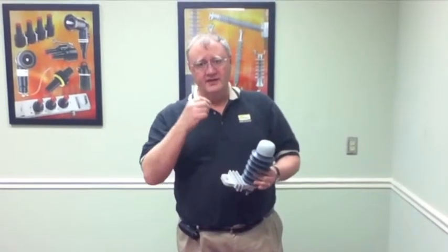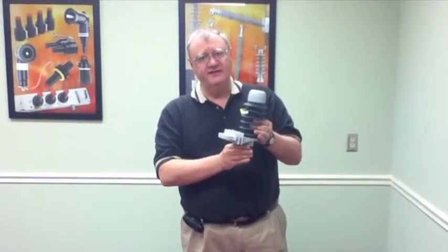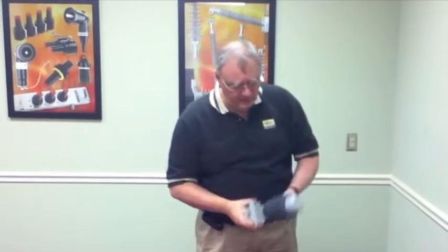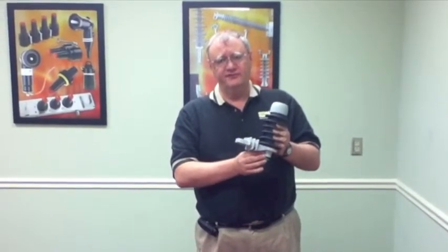However, if there does happen to be a failure from system-related causes or excessively high energy, the Ohio Brass surge arrestor has the best disconnecting device in the industry. A number of years ago, we made a very small change to the disconnector technology where we replaced the prior technology of a resistor for grading with a high voltage capacitor. This has made the design guaranteed to clear. In over five million arrestors that have shipped, there has never been one instance reported where one of these arrestors failed and did not clear.